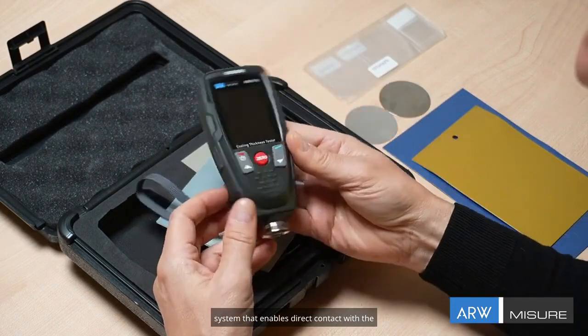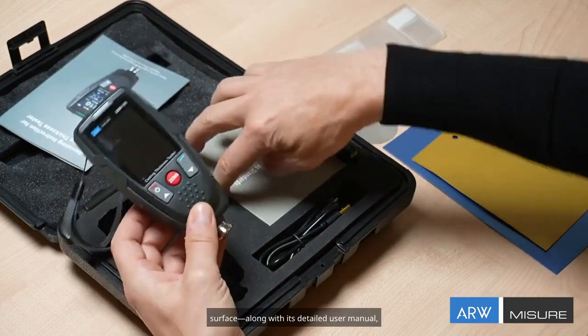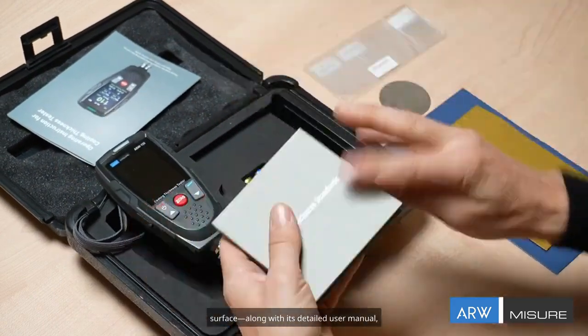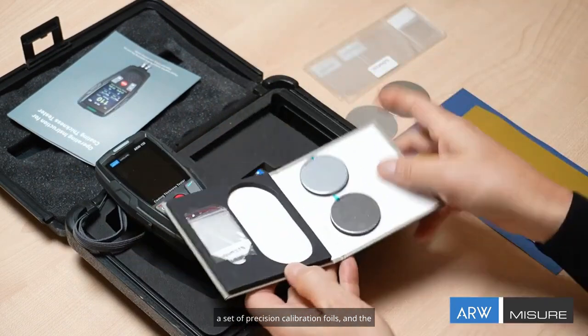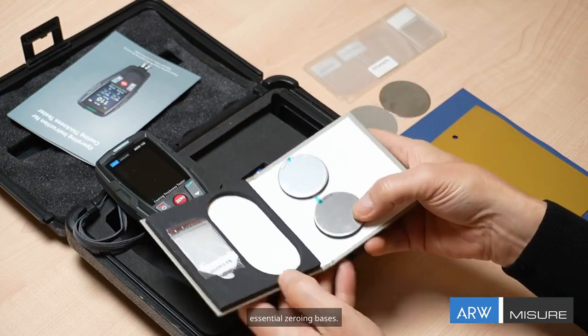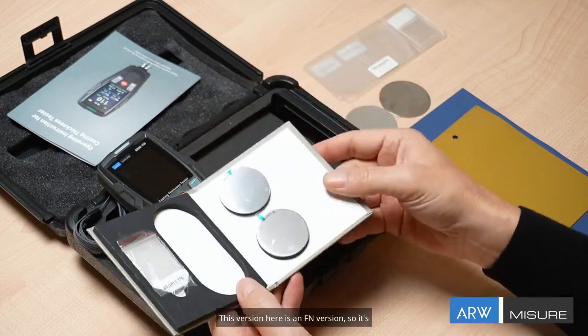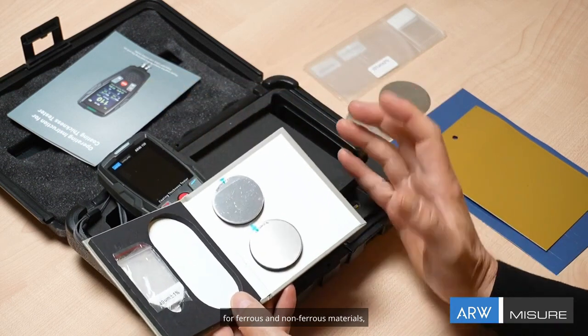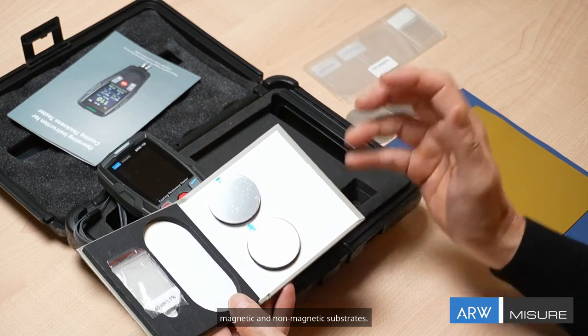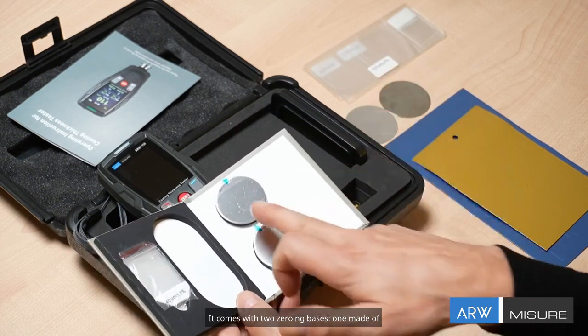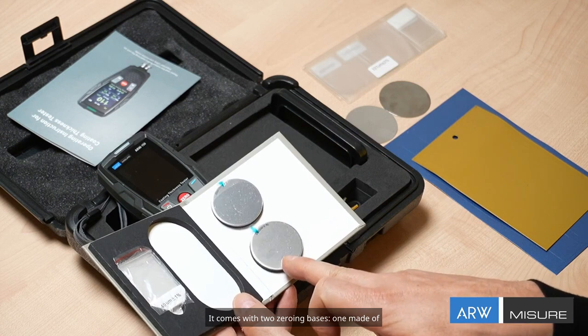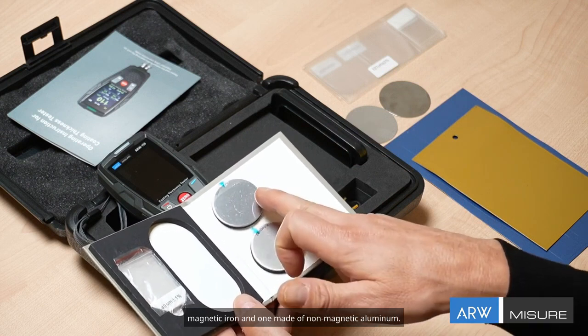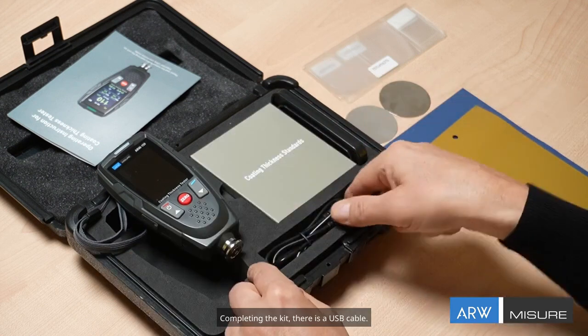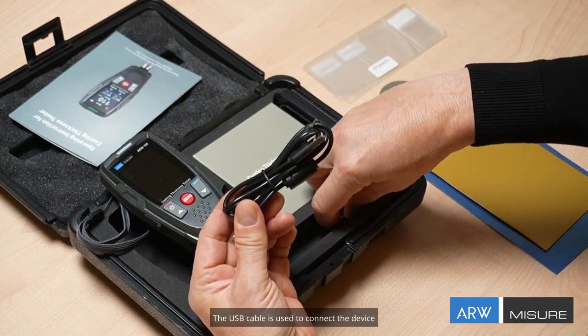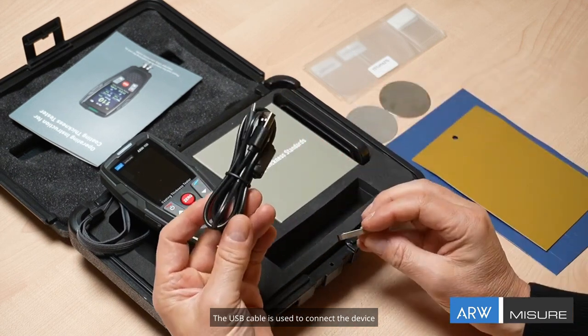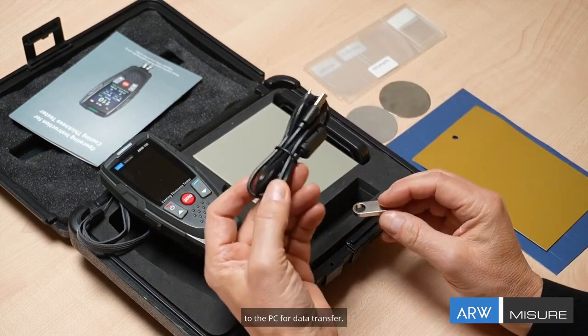system that enables direct contact with the surface, along with its detailed user manual, a set of precision calibration foils, and the essential zeroing bases. This version here is an FN version, so it's for ferrous and non-ferrous materials, magnetic and non-magnetic substrates. It comes with two zeroing bases, one made of magnetic iron and one made of non-magnetic aluminum. Completing the kit, there is a USB cable. The USB cable is used to connect the device to the PC for data transfer.